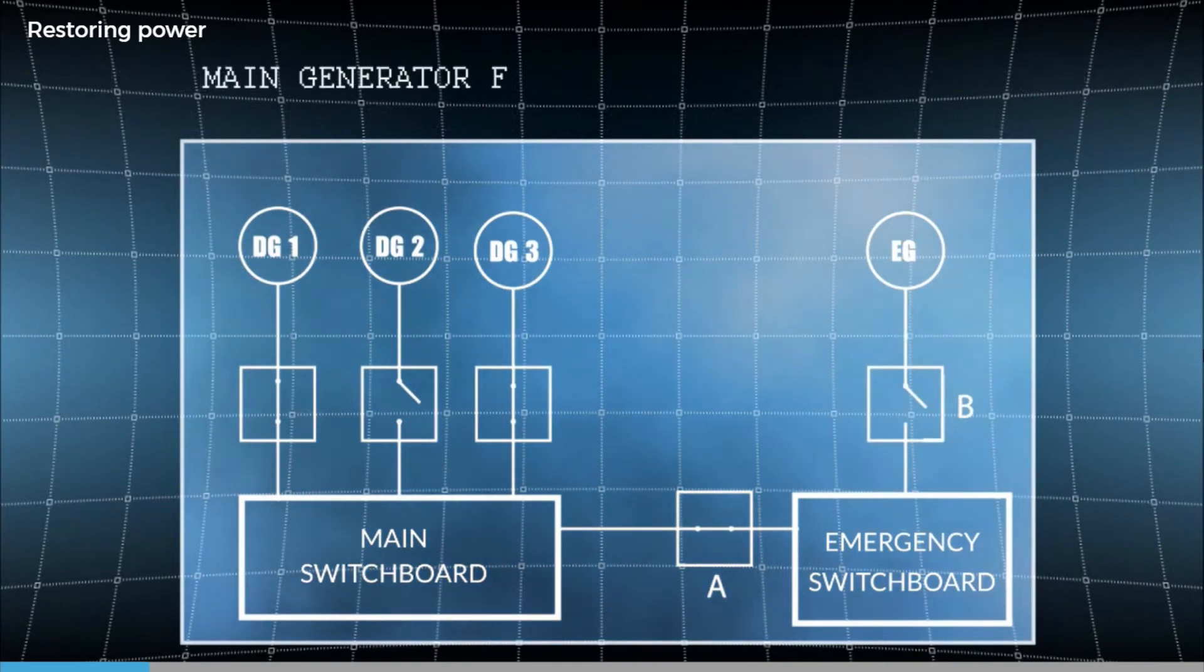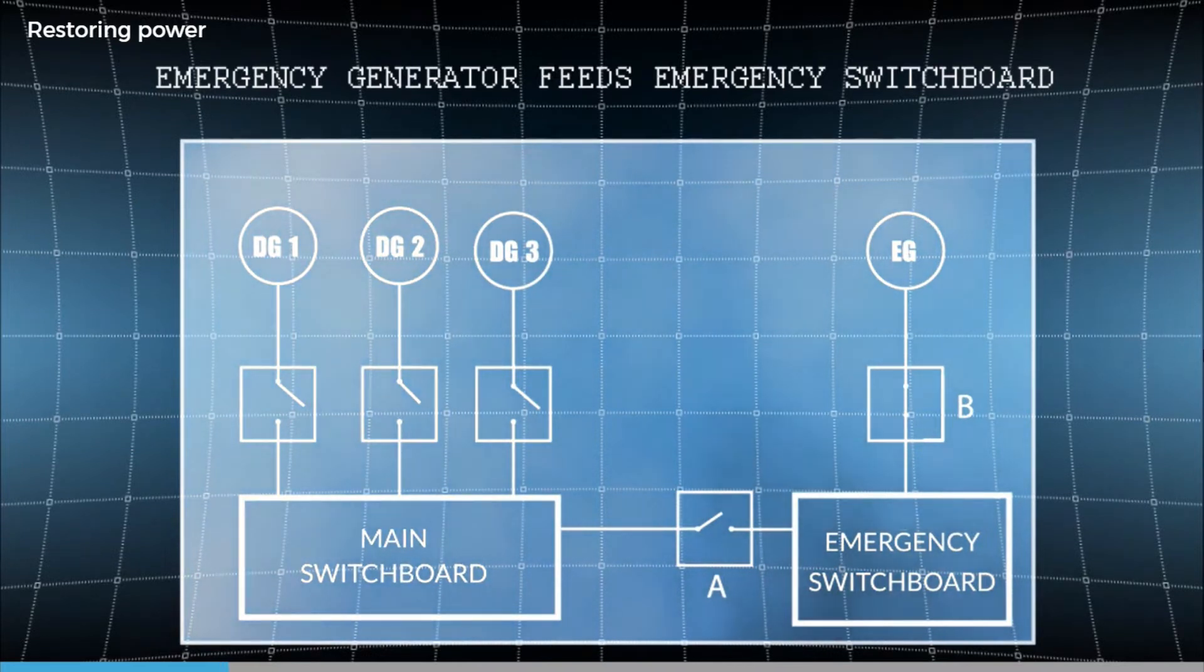This means we can feed the emergency switchboard either from the main switchboard or the emergency generator. What we can't normally do is backfeed the main switchboard from the emergency generator.